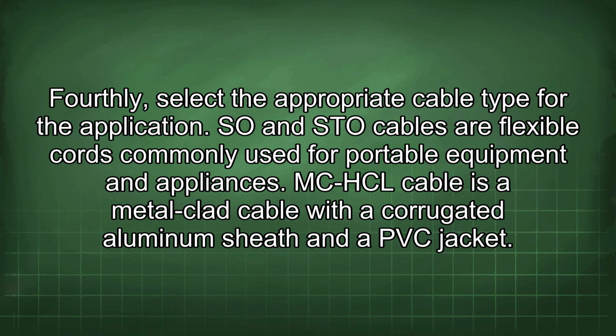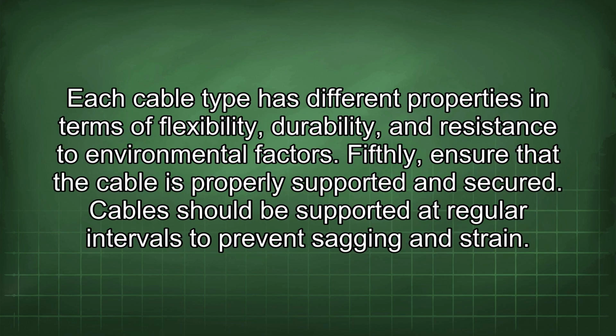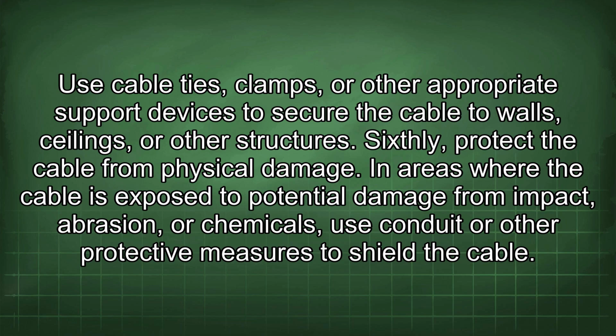MC-HCL cable is a metal-clad cable with a corrugated aluminum sheath and a PVC jacket. Each cable type has different properties in terms of flexibility, durability, and resistance to environmental factors. Fifthly, ensure that the cable is properly supported and secured. Cables should be supported at regular intervals to prevent sagging and strain. Use cable ties, clamps, or other appropriate support devices to secure the cable to walls, ceilings, or other structures.